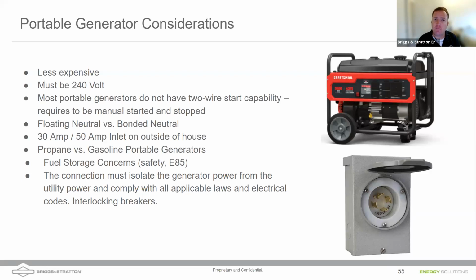Keep in mind that a lot of times this may be a gasoline generator, but a lot of times they're known as dual fuel, where you can get the propane tank from your barbecue essentially and use that to power the generator. I like that example because a lot of times people buy a portable generator, they're all excited, bring it home, start it up, and then let it sit for a year or two until the outage comes along, and by that time all that fuel has gone bad and the carburetor's all gummed up. By using a gaseous fuel like propane, once you start and stop the generator, all of that just evaporates and goes away.